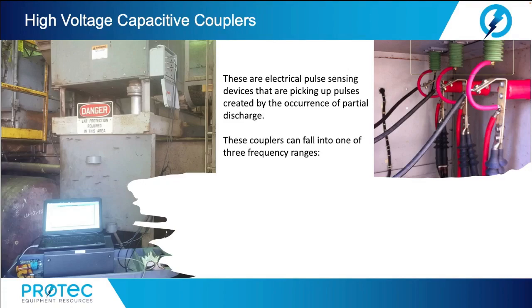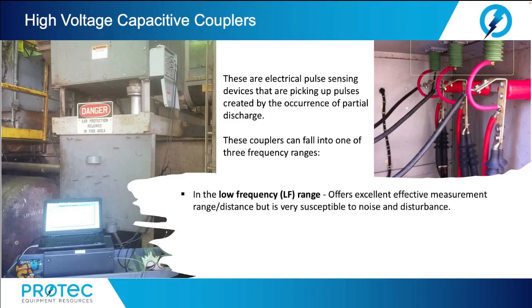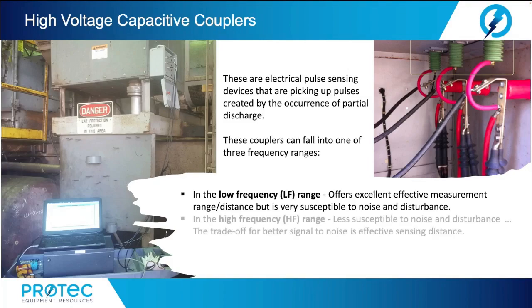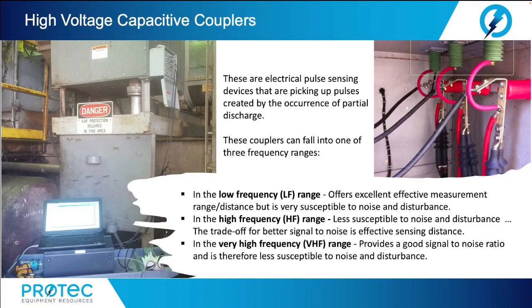These couplers can fall into one of three frequency ranges. In the low frequency or LF range, they offer excellent effective measurement range distance, but are very susceptible to noise and disturbances. In the high frequency or HF range, they are less susceptible to noise and disturbances. The trade-off, though, for better signal to noise is the effective sensing distance. And in the very high frequency range, they provide a good signal to noise ratio and are therefore less susceptible to noise and disturbance, however, with the trade-off of effective sensing distance.